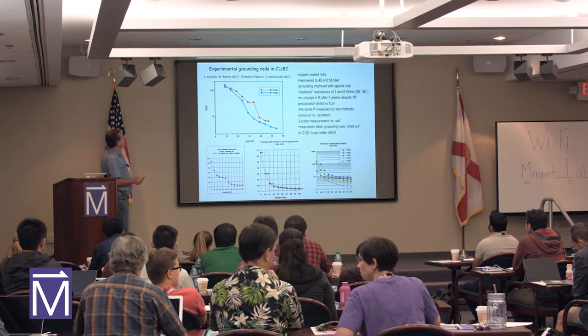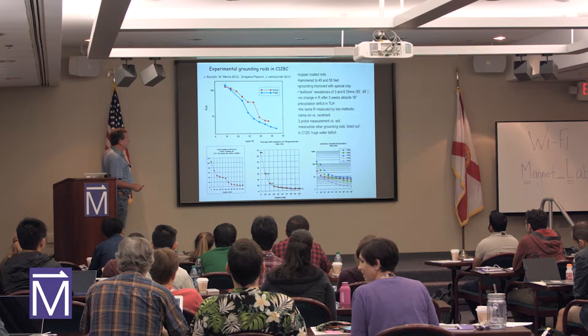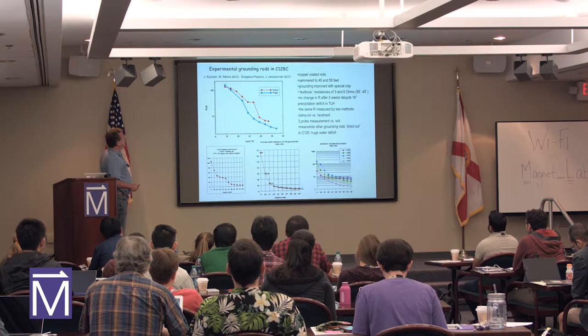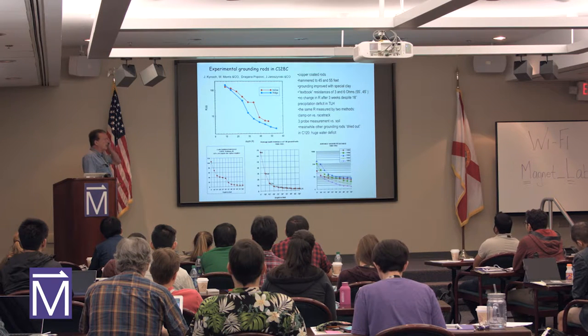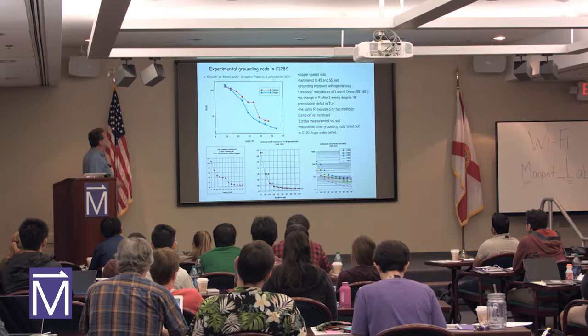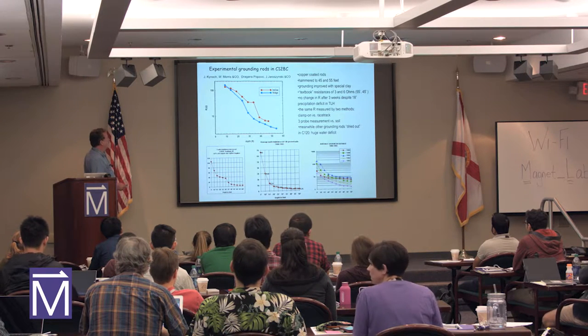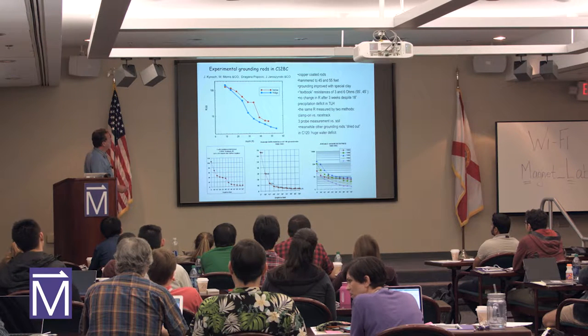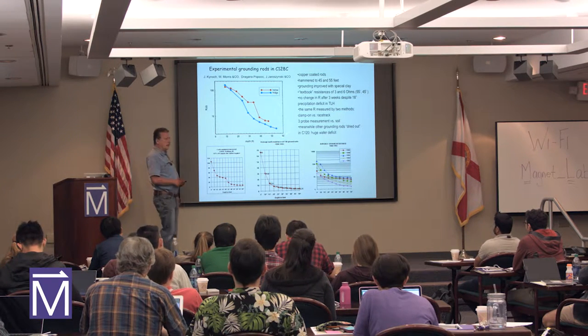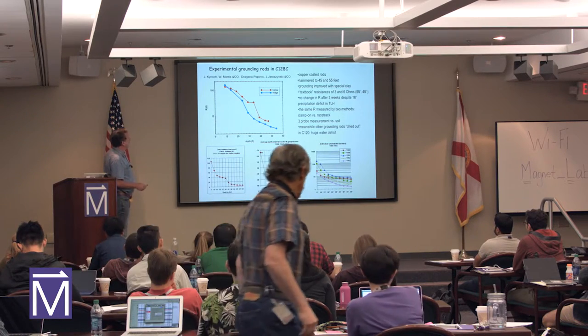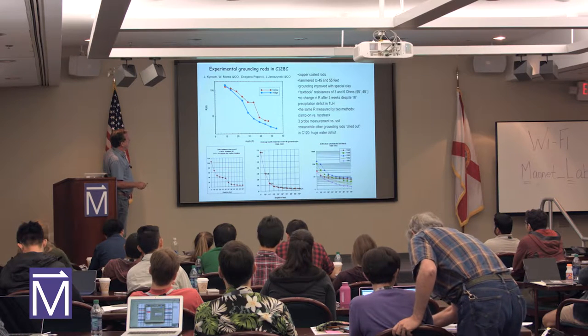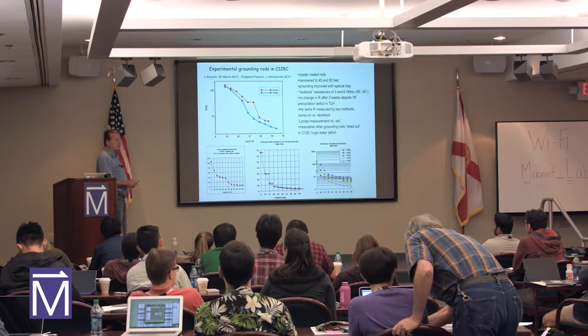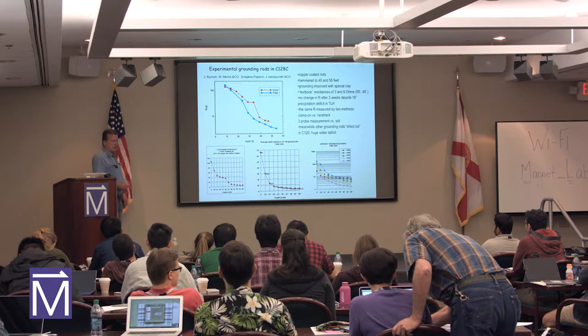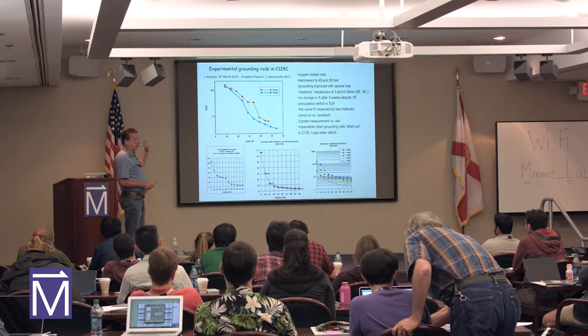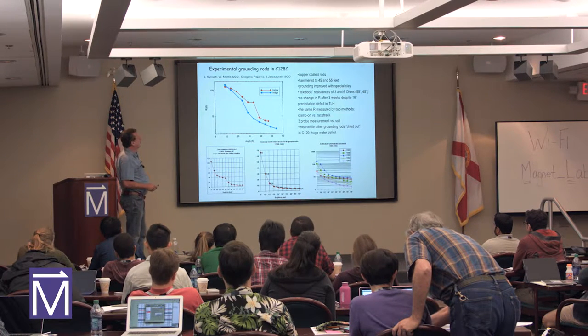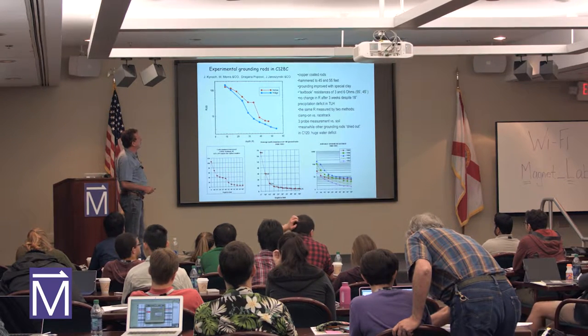So we made grounding rods first in one of the places. We put 20 feet long copper rods into the ground and measured their resistance when we hammered them deeper and deeper. And here there is resistance versus depth. Sorry, it was 20 meters, not 20 feet. So somewhere well above 30 feet, we are coming to the desired few ohms resistance. This depends on the ground, of course. Here the ground is not good because it's sand and there is porous limestone below, somewhere at 20 meters.